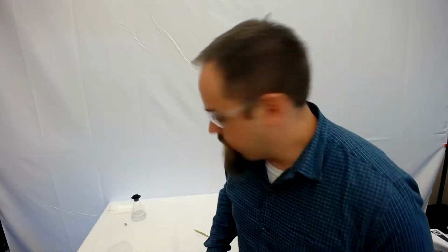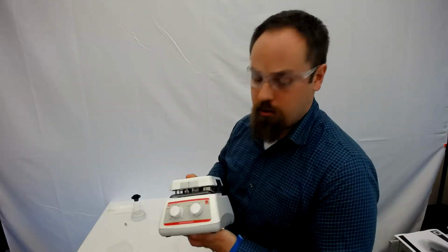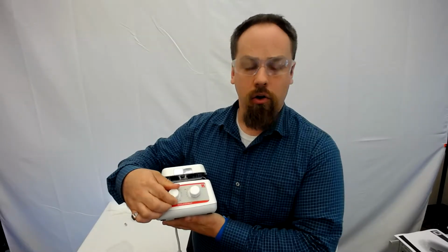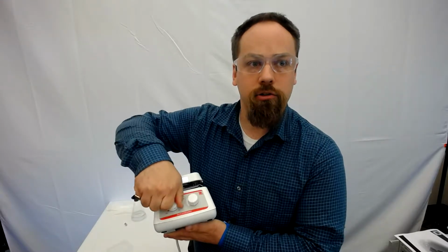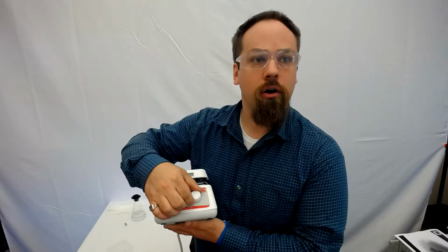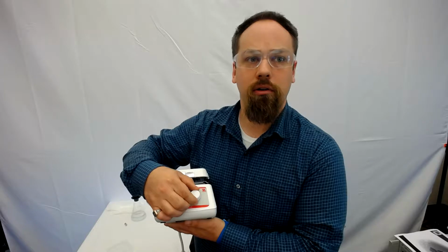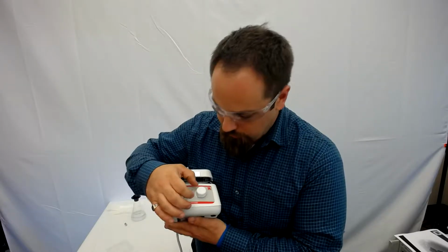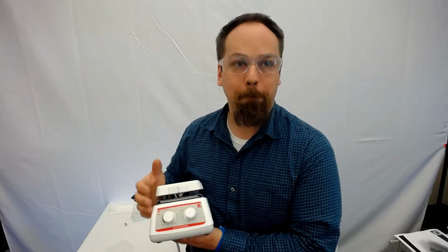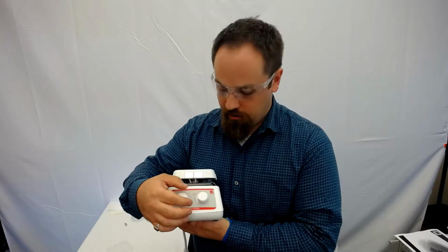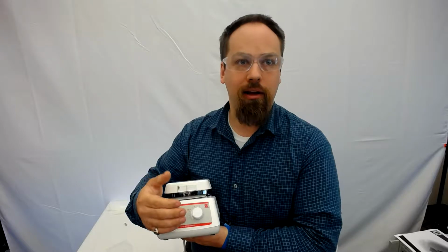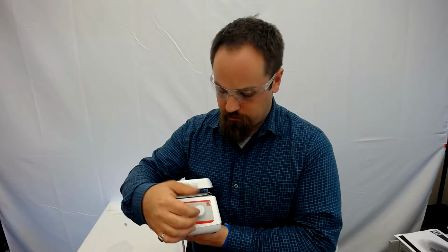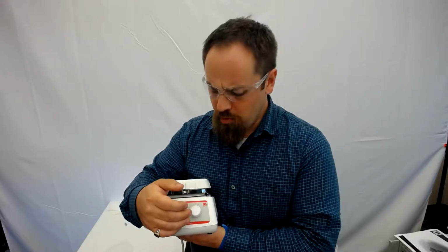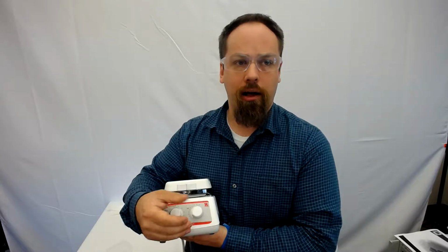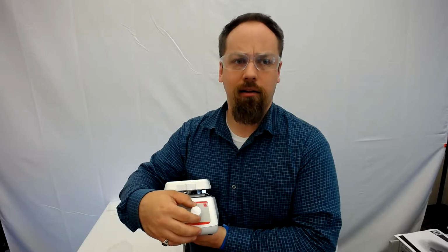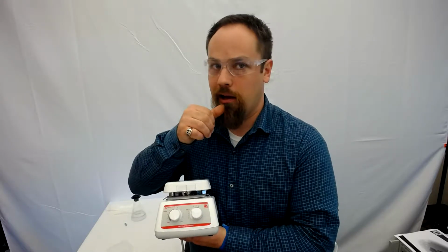So to familiarize you with this unit, this is an analog unit. Here you have the heat on, off, and control knob, and the stir on, off, and control knob. With stir, you can hear a definite click between the on and off, and then a linear scale. Now, on the analog units, this linear scale does not mean that you're necessarily going to get a linear output from that scale. So it's important that as you turn it on, we're only really calibrating this at low speed, and we are testing at low speed, mid speed, and high speed.